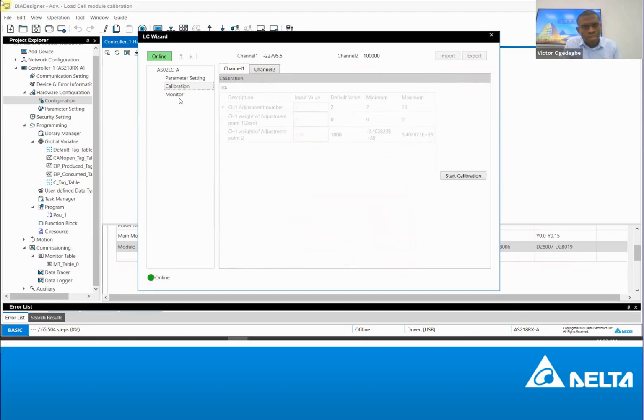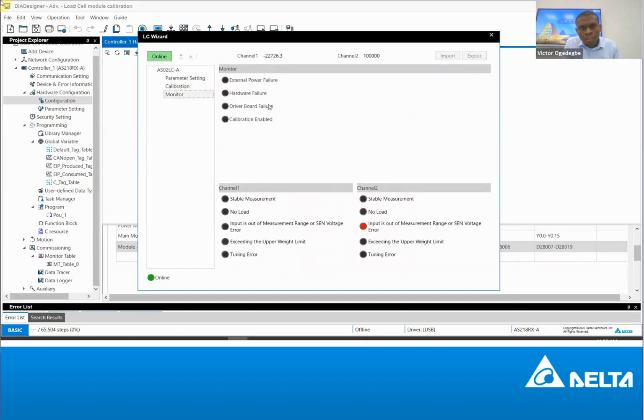Okay. Then how do we calibrate? You just go to calibration. Let's say monitoring. Yeah, I have some error. That's what you can also see on the CPU. Input is out of measure range or sense voltage error. Maybe the sense voltage cable is not well connected. So this monitor gives you what is probably happening.